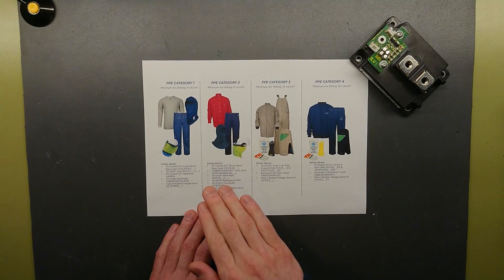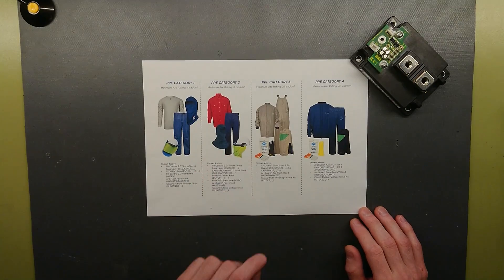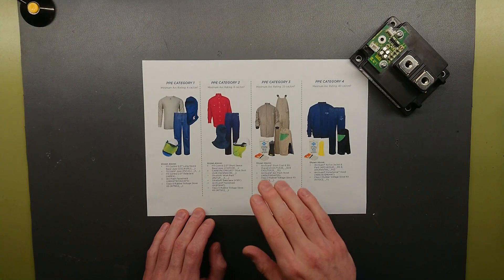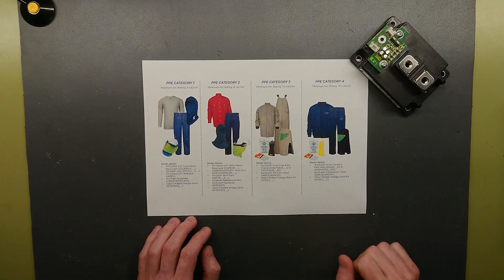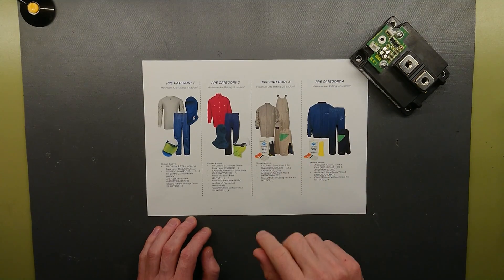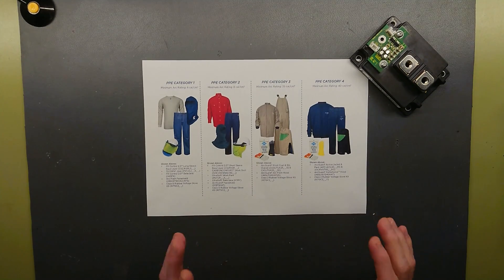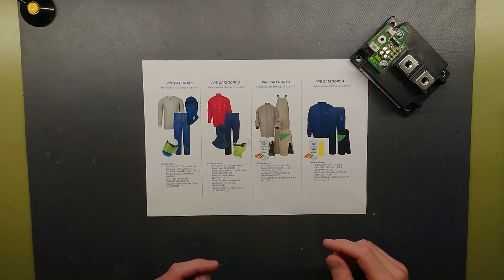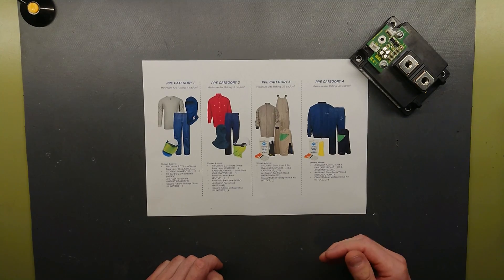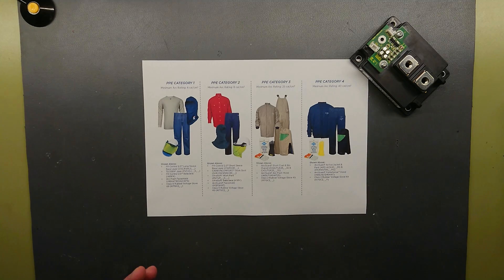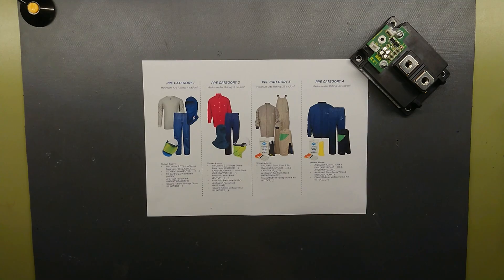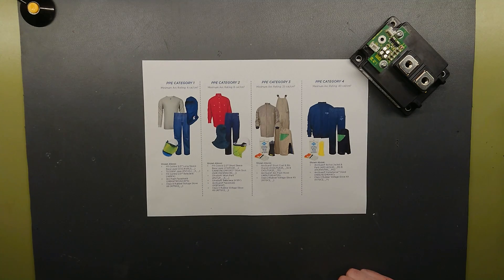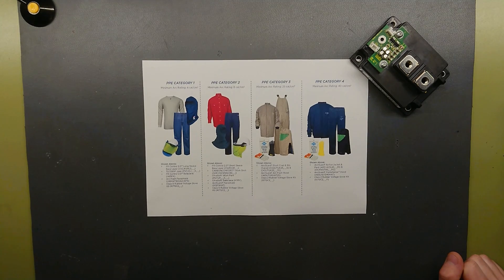But now with current limiting fuses we are getting down in the categories. We are down to only wearing full flame retardant suit with a helmet and visor, not these bomb suits that are absolutely impossible to work in. It really makes working easier and safer by making short circuit energies lower but also that you are wearing no more PPE than necessary to protect yourself, and you are able to actually work.